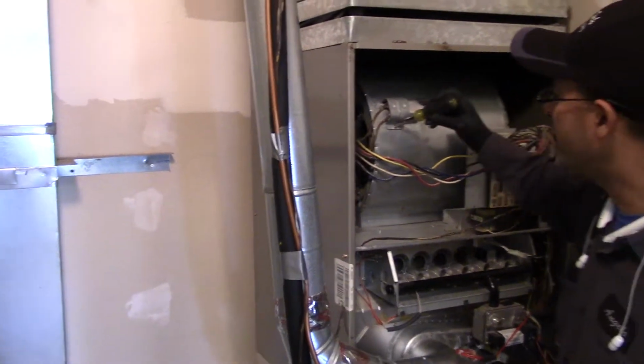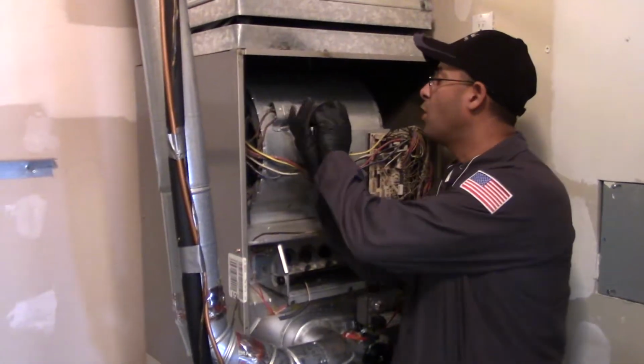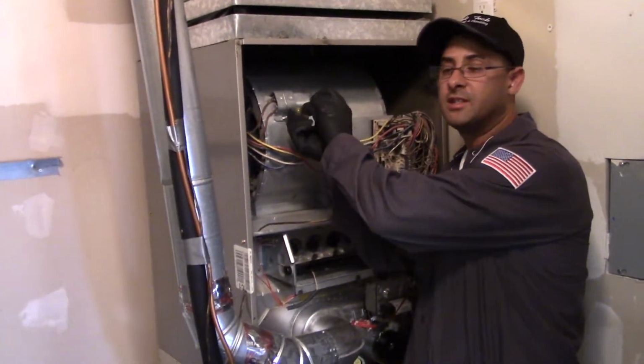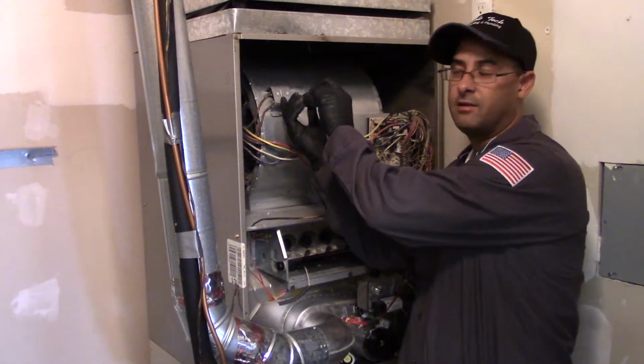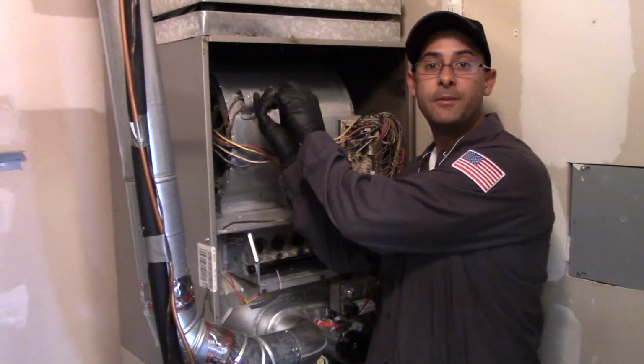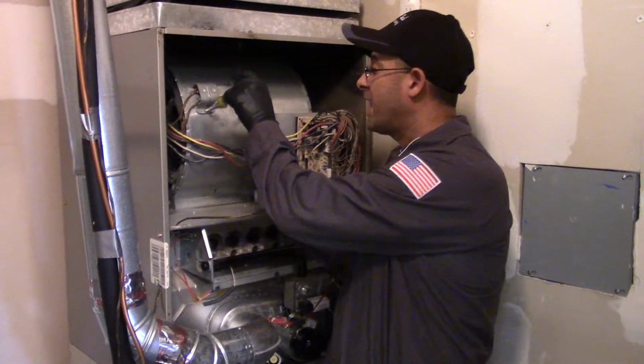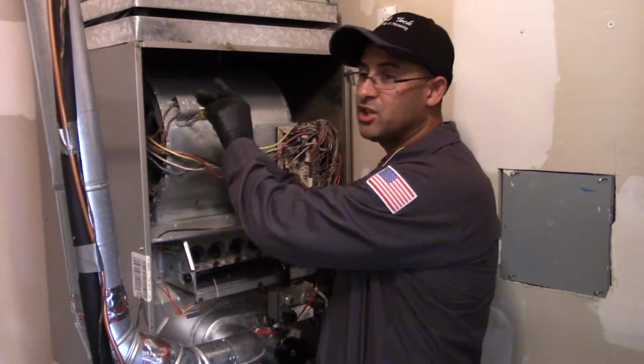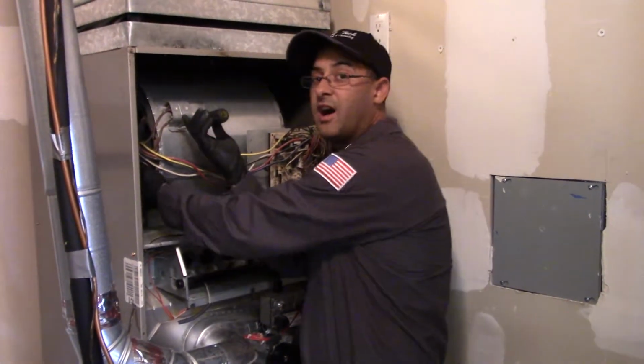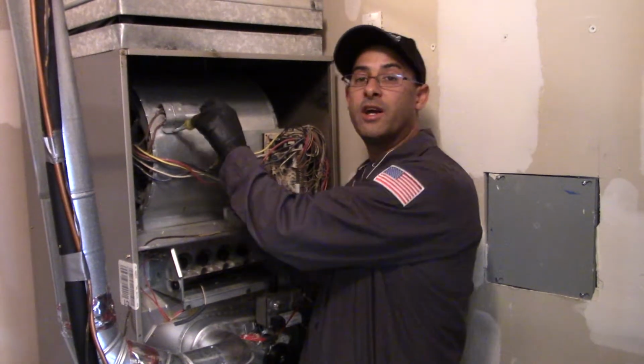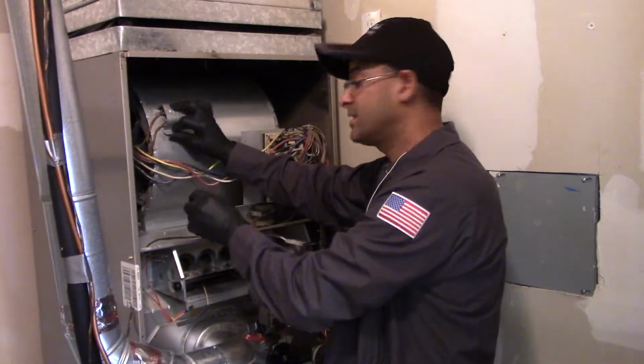On that capacitor, if it's low or out of range, the motor will actually have high amps and overheat. When it has high amps and overheats, it might shut off and just not work, and it's going to be really hot to the touch. They call that internal overload, which is protecting itself.